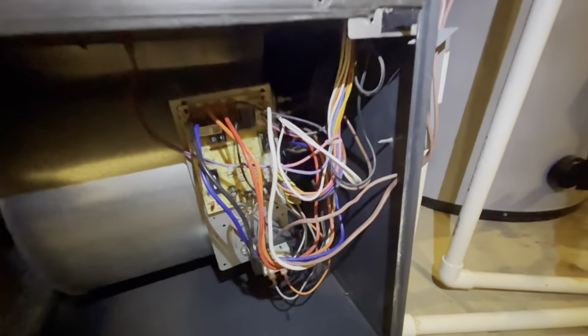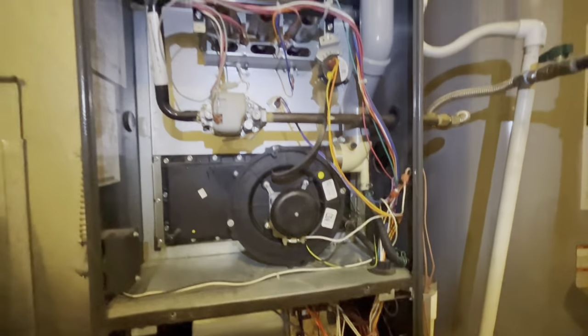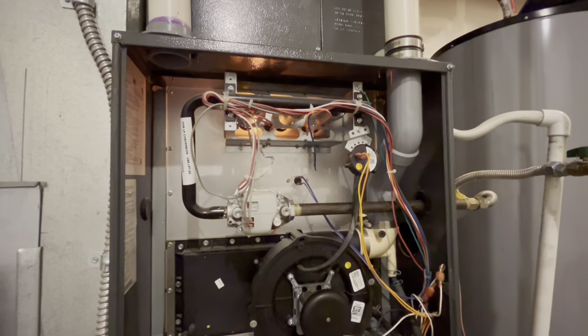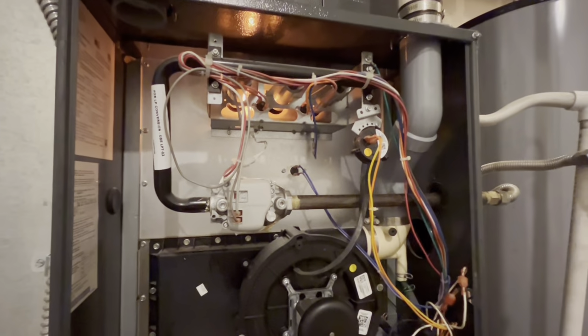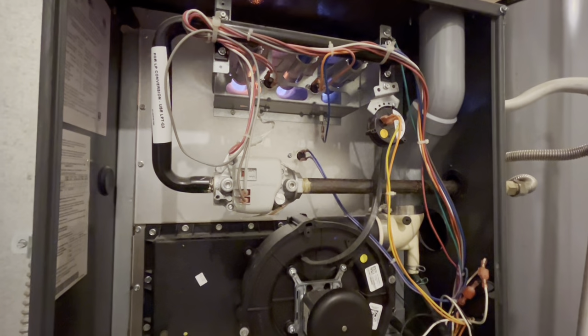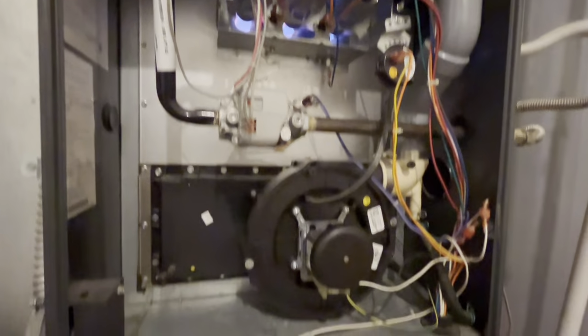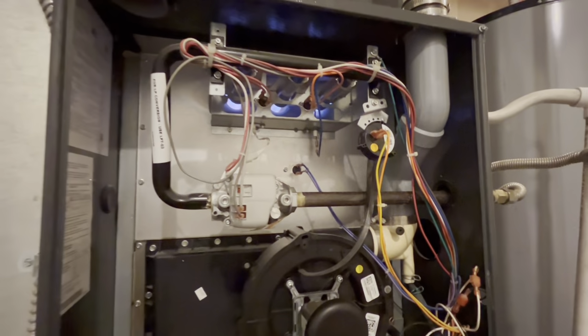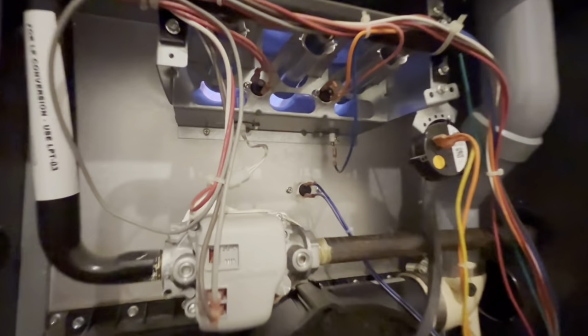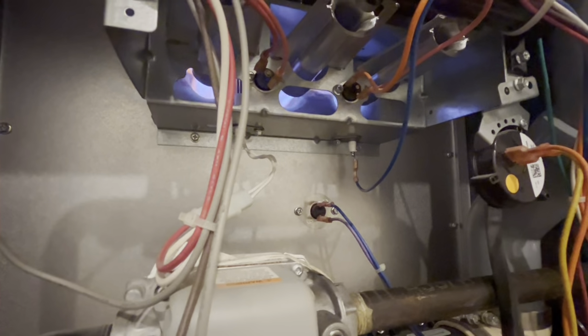But you need to make sure that you set up the speed tap wire correctly to how it was before, or you need to match it to the furnace. If it is a 1/3 horsepower motor, you need to set it to 1/3 horsepower. It can go to a 1/2 horsepower. It can go down to lower. So it may not be always black for cool or blue for heat. It may be red or orange or something like that.